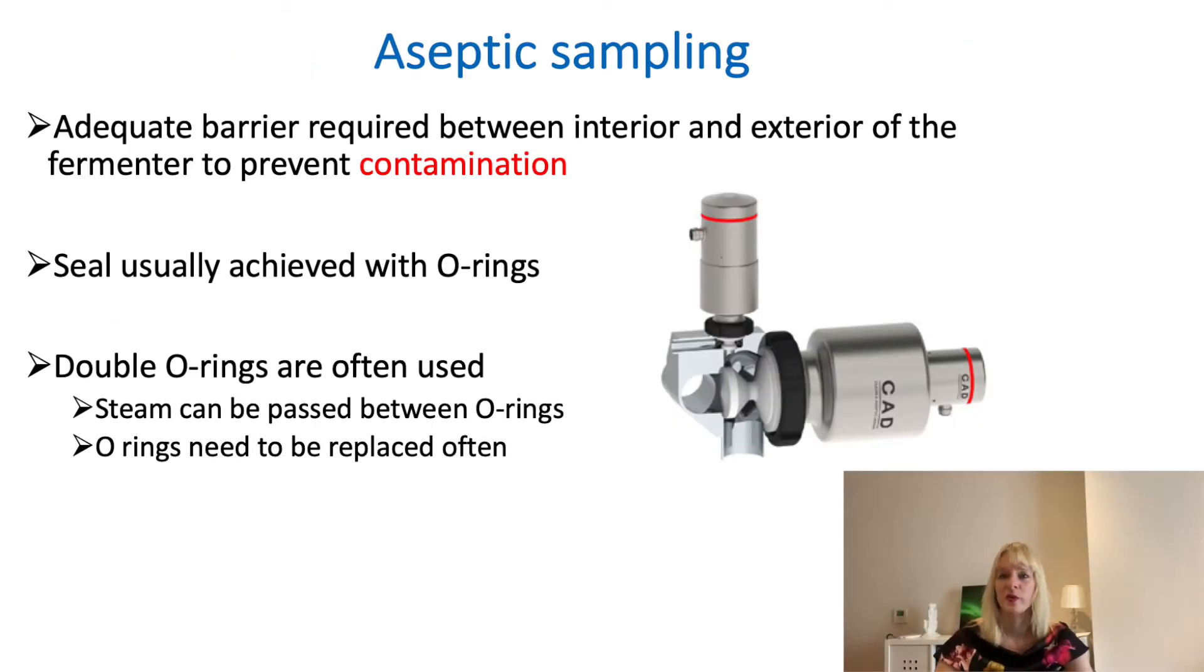Another way of preventing contamination is using aseptic sampling. Aseptic sampling often involves at least one O-ring, usually two of them, so you really separate out the interior of the fermenter and the outside. You can use steam to actually clean those, so you sterilize them in between, but the O-rings make sure that you really seal off the reactor. What's the most common problem here? People not replacing O-rings. If you work with that kind of principle which is very good to prevent contamination, they need to be maintained quite on a regular basis.